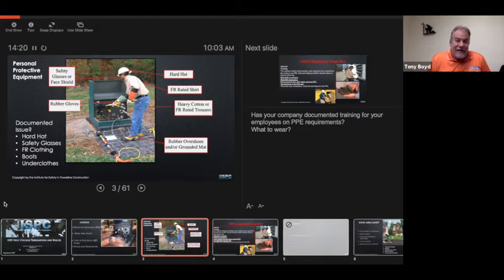And the answer is certainly not everyone requires that. The rubber overshoes are basically to enter and exit that grounding mat. So they're a good idea. I'm not going to give my personal opinions about what the rubber overshoes do, but they do provide some protection. How about rubber gloves? You see he's using a hot stick with rubber gloves. ISPC has never been a proponent of wearing rubber gloves when using a hot stick. And you notice it's a shorter hot stick. Most of the shotgun sticks nowadays are 8 foot long, which gets you back away from what the hazard actually is. So we do not require rubber gloves with hot sticks.